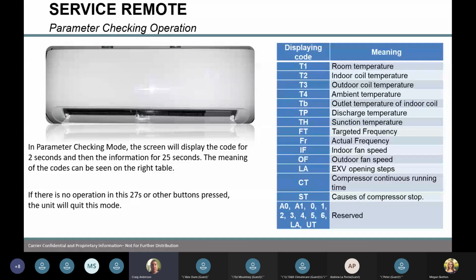You can check indoor fan speed. You can check the frequency of what the compressor is doing outside to give you an idea of what stage it's in. And your E valve, is it open 100% or is it open 80%? So great things you can do by the remote control, but you need to sit and play with it in front of a unit.